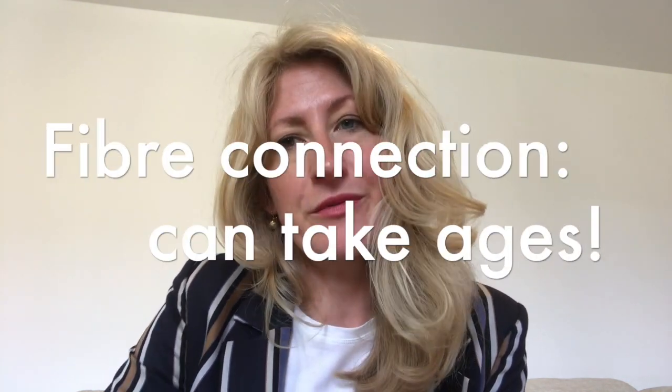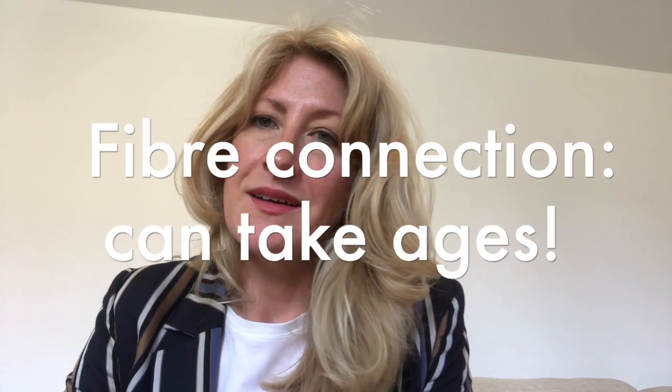The utilities company can help you do that, or someone that specialises in utilities and groundworks, which is what someone helped us with in Milton Keynes. So yeah, have a think about that because that's something to consider. Your fibre as well is worth considering early on, because you've potentially got to get wayleave agreements. A wayleave agreement basically allows you to get the fibre onto your site, going under a public area, a footpath, a road. So the fibre company need to be able to access your land.